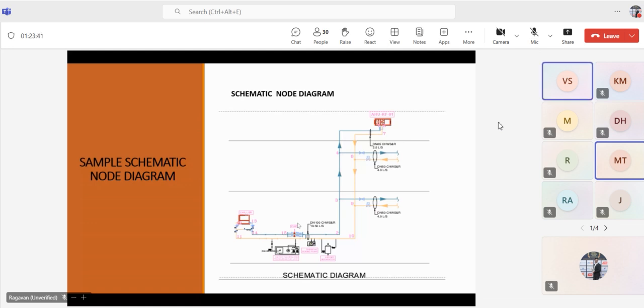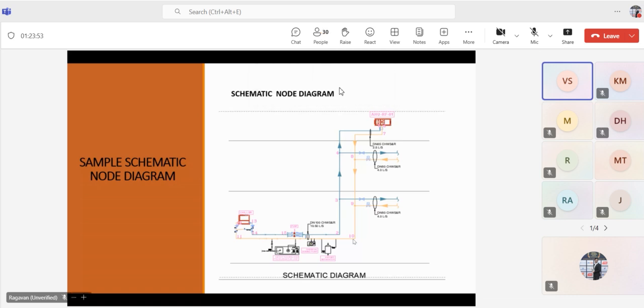When you have primary and secondary, you have to do both because I want to select both pumps, right? For example, the primary side goes to the supply and the return comes back to the line. The primary pump mainly focuses on the return line. If you have a return line that the secondary pump cannot manage, the primary pump will take on that pressure loss. So the entire return line, the longest path of the return line up to the chiller, including the primary pump. Additionally, the chiller line, because it will go to the chiller line again, right? Similarly, for the secondary pump, starting from the chiller to the supply end, the longest path on the supply side. So you get both like this.